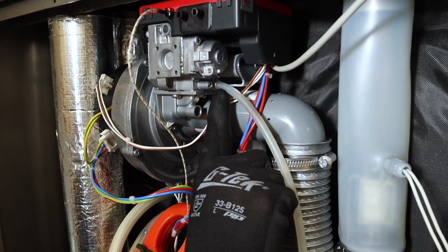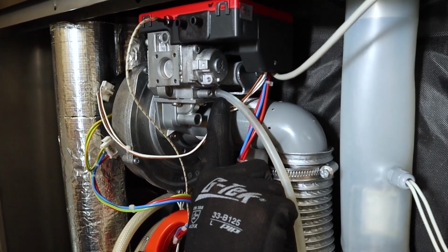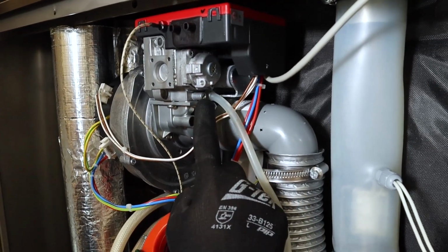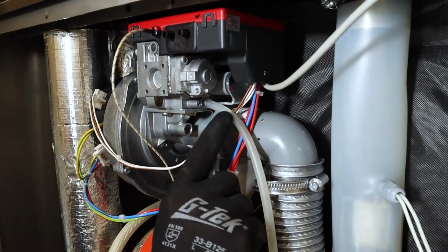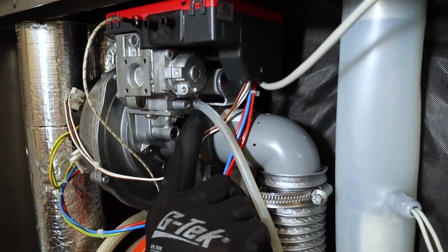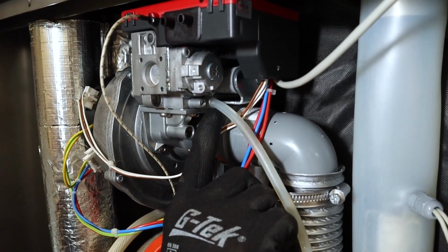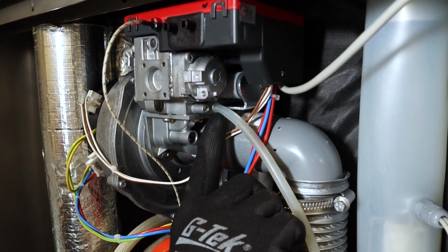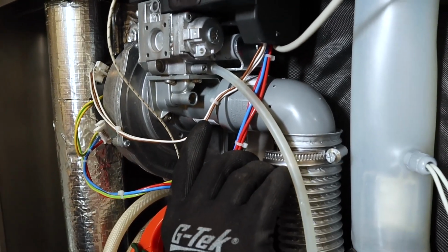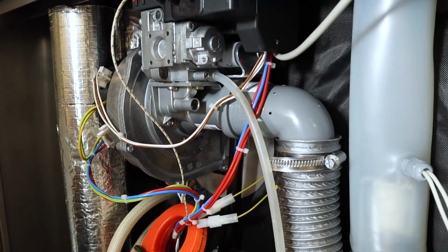Of course, I would want to go ahead and shut off my gas supply to the Combi so that I can crack the little screw loose and then hook my gas tube up over that port. Remember, for checking incoming gas pressure, it's going to be our right side port, as you can see shown here. So like I said, I already have this hooked up for us.